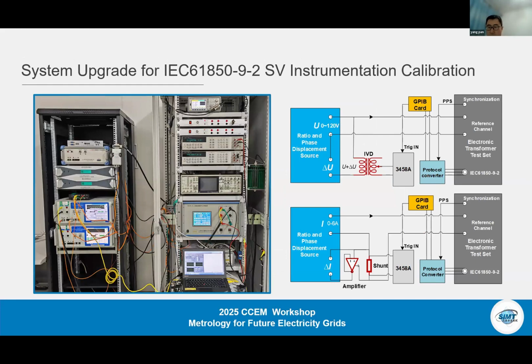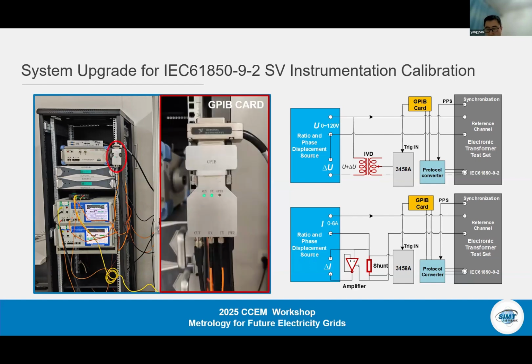So in order to ensure simultaneous sampling by the DMM and packet transmission, enabling real-time transmission of all data acquired within each second, we developed a synchronous data acquisition GPIB card and a protocol converter around 2020. The primary function of the GPIB data acquisition card is to translate control commands into IEEE 488 compliant control instructions, enabling real-time control of the DMM via the GPIB interface. This ensures continuous sampling and data output while maintaining synchronous sampling.